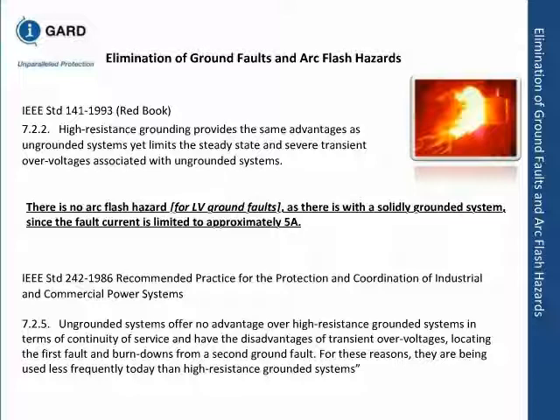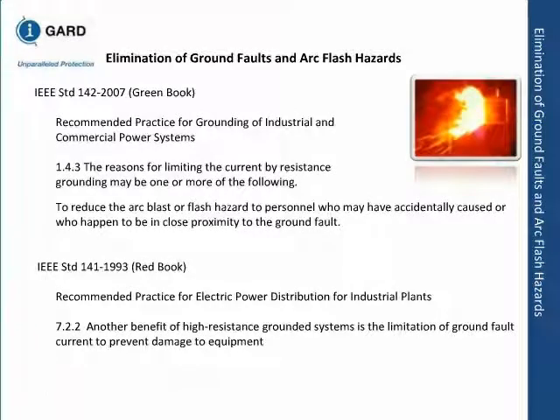The Green Book, which was just revised last year, and I'm the vice chair for that book, tells you the same thing. The reasons for limiting the current by resistance grounding may be one or more of the following. One is always continuity of power. Second is arc blast or flash hazard. If in your facility you saw that motor terminal boxes or enclosure doors flew apart during a fault, that is because of a solidly grounded system. It should not happen if the fault is cleared in a high-resistance grounding system. And 141, the Red Book, essentially says the same thing: limitation of ground fault current to prevent damage to the equipment and prevent injury to people. So all the good qualities are available as opposed to a solidly grounded system.